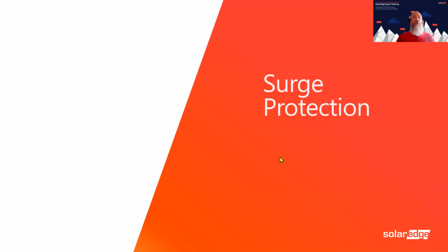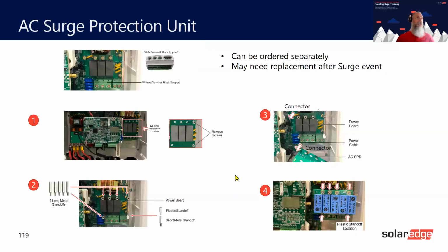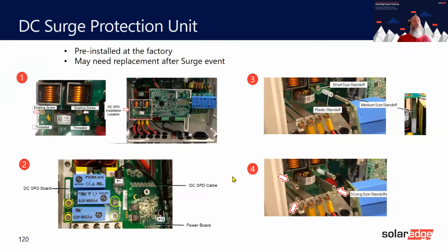Okay, so let's move off to surge protection. Now, I spoke to you earlier and I said that we had some surge protection. I think it was one of the first slides I showed you. And we do. The new, when I say new, the SE 25, 27.6, 30, 33.3, and 40 all have DC surge protection. I'll just go down one. DC surge protection as standard on the inverters. Okay, and that is on the left hand side here, and that would be this device here. And it basically plugs in. It's a sacrificial device. It plugs in and it stops any surge currents or surge voltage from damaging the inverter. Once it's been used, it will report in as an error that it's happened and we need to change it, things like that.